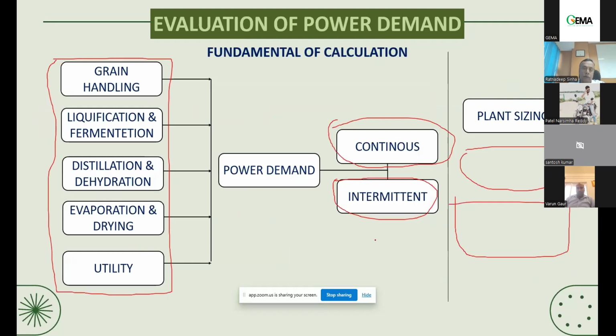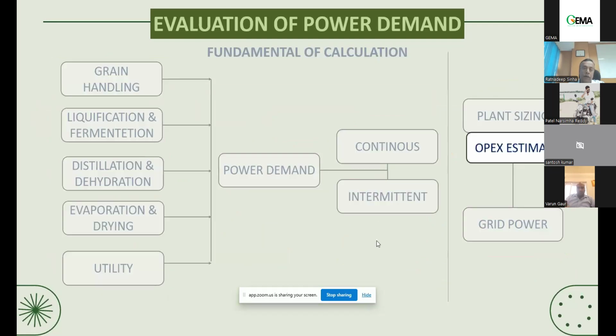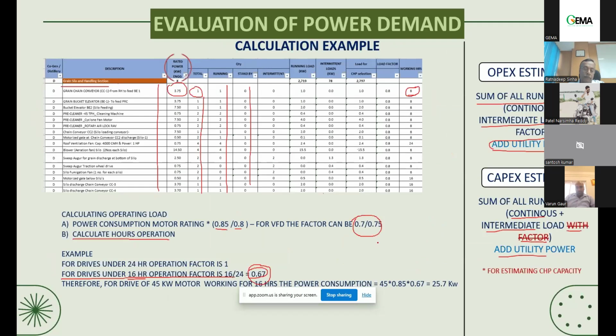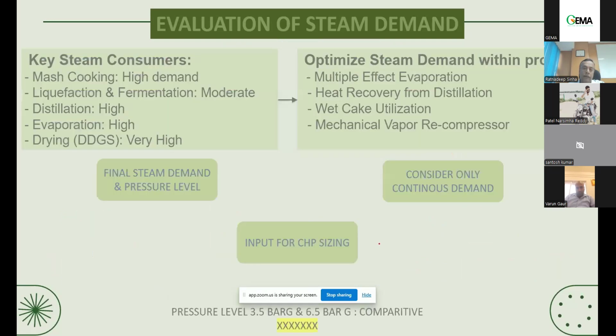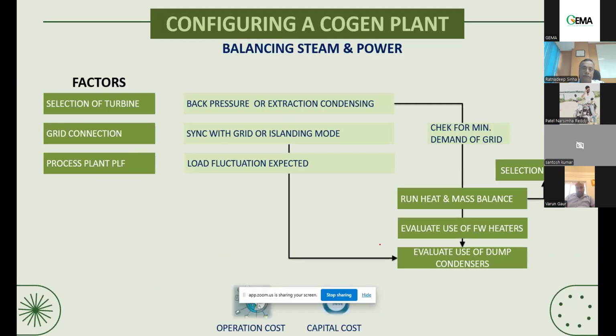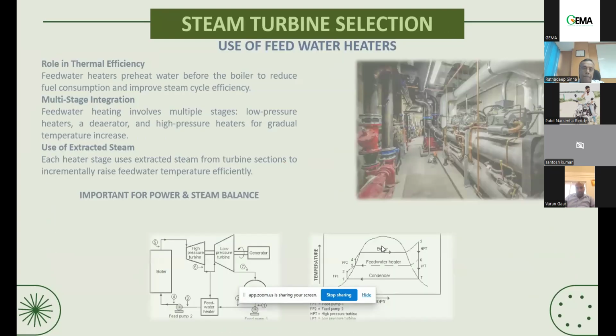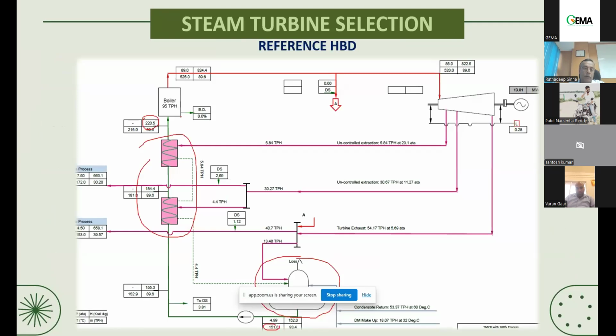So that is why in many cases, particularly on the higher side of megawatt, where we are going for a 13 megawatt, 15 megawatt unit, we should put at least one HP heater. And secondly, we can combine the extractions. Suppose for this particular case where we are discussing, from there also I am taking an extraction at 7.5 bar, and also I am taking extraction from here, which is going to the process.